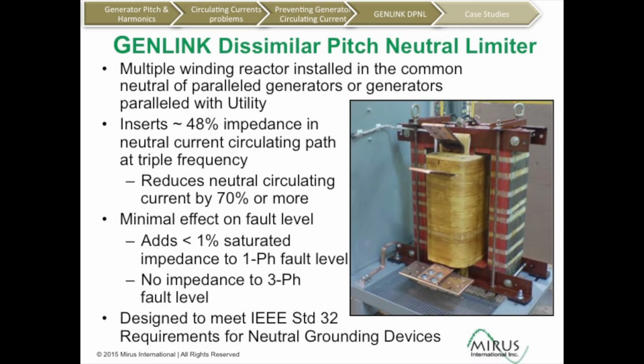There's a minimal effect on fault level, and this is intentional. So when the reactor is saturated during fault conditions, the impedance to fault currents is less than 1%. So it will not change your protection scheme or require change to your protection scheme. And it has no influence at all on the three-phase fault level. And we've built and designed these to IEEE standard 32, which is the requirements for neutral grounding devices.